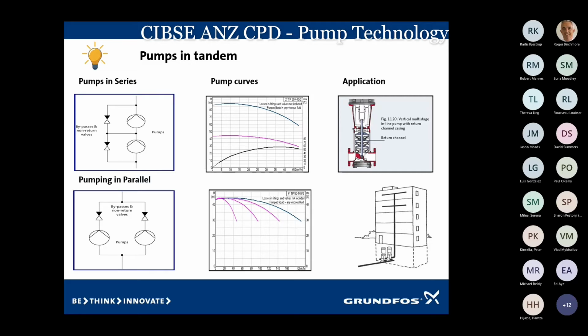If we took two pumps now, the same size pumps, and put them in parallel, we have a common suction feeding two pumps and a common discharge. We now double the flow rate, but the head stays basically the same. If we have too high a friction loss in the discharge when you run two pumps, then you may not double the flow rate, but in general that's what will happen, you'll double the flow rate. This is why we use booster pumps. Always remember, put a non-return on each pump. If we don't have a non-return after the pump, one pump can then poke water back down into the head of the other one, and then we have a problem.